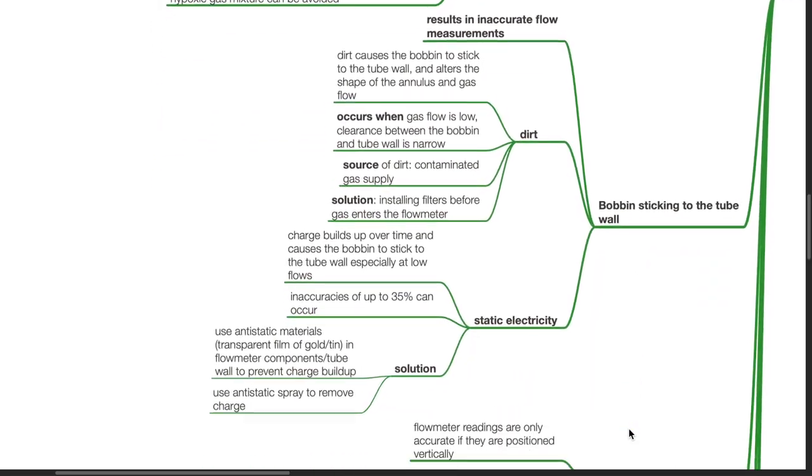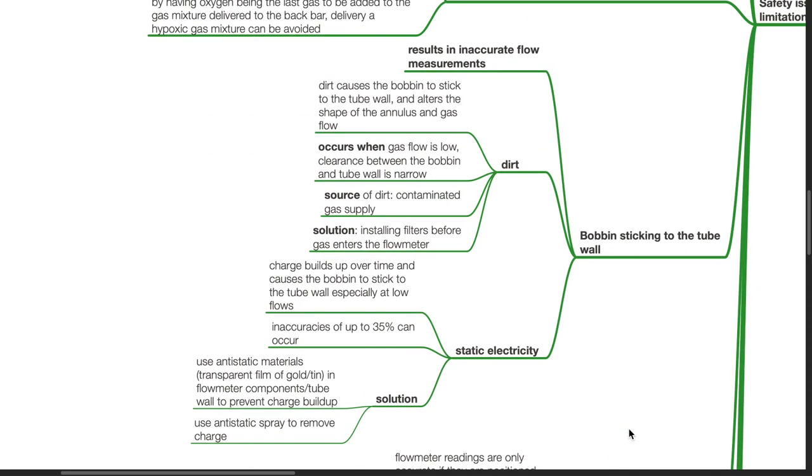Bobbin sticking to the tube wall results in inaccurate flow measurements. It can be caused by dirt or static electricity. Dirt causes the bobbin to stick to the tube wall and alters the shape of the annulus and gas flow. This occurs when gas flow is low.